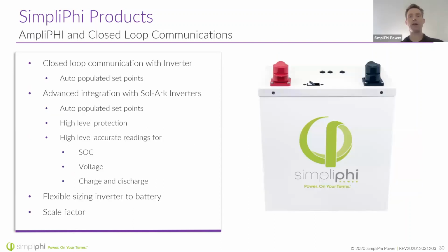So for that, we recommend using a battery like our AmpliPHI battery. If you need an outdoor rated battery, our AmpliPHI battery is a good choice. These batteries have the closed loop communications I've talked about, and they have auto-populated set points.